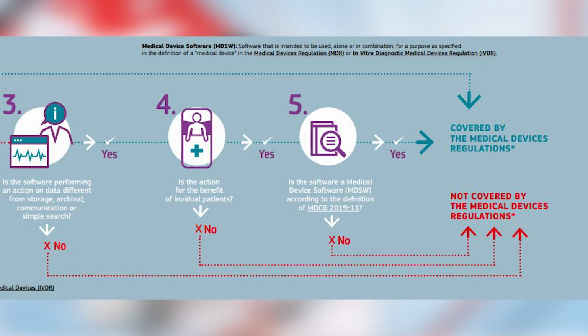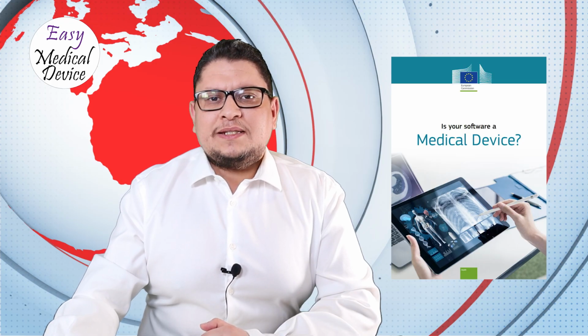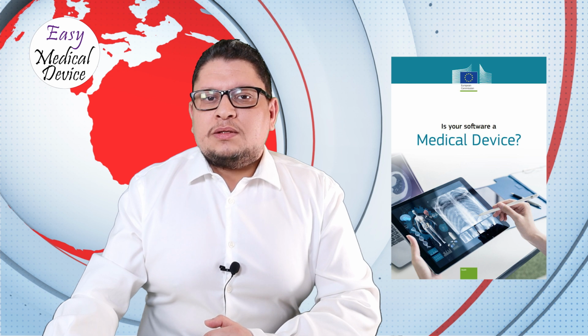Then: is it software that is under the definition of a medical device software? So you have two definitions. You have the definition of a software and you have the definition of a medical device software in the guidance. You have to check both definitions to see if they are applicable. If yes, then it is covered. If no, then it's not covered.